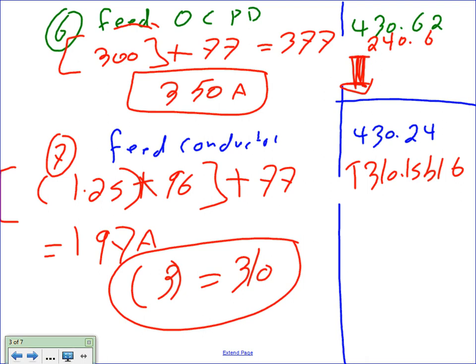Some people, guys, come, look, Chris, we size the feeder based on 197. What you were showing me the other day, that sheet, they size it instead of 197, they match it to the overcurrent protection device, 350. Can you guys see the difference between 197 and 350? Major difference in terms of amps. If you do 350, your conductor here, Chris, probably 500 kcmil. We went from 500 kcmil to 3/0. Major difference. And there is a reason why they do this, guys.